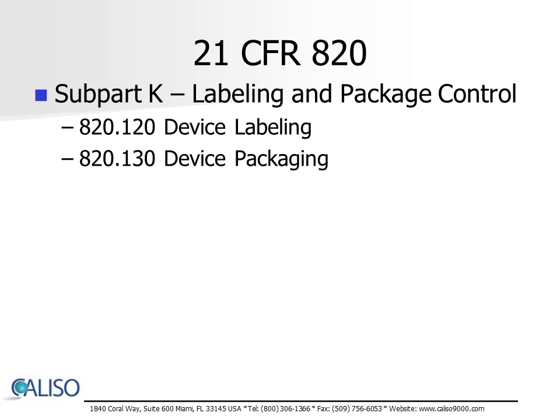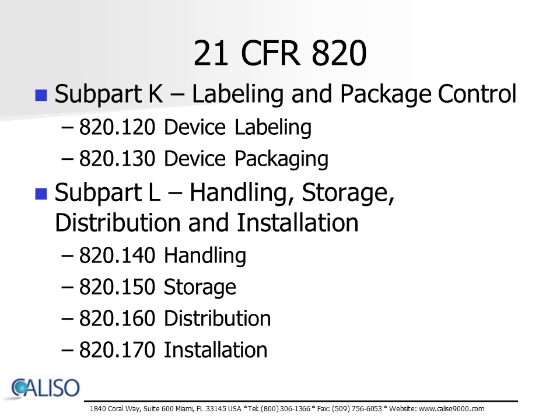Subpart K, Labeling and Package Controls. This section speaks directly to the requirements for not only device labeling, but also device package labeling. Subpart L contains the requirements for handling, storage, distribution, and installation, as applicable.